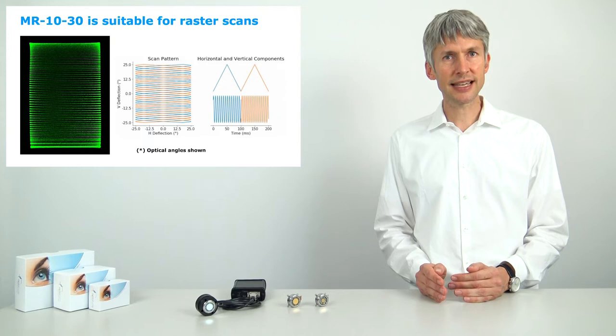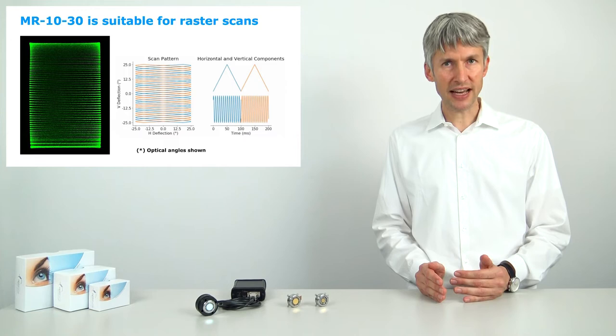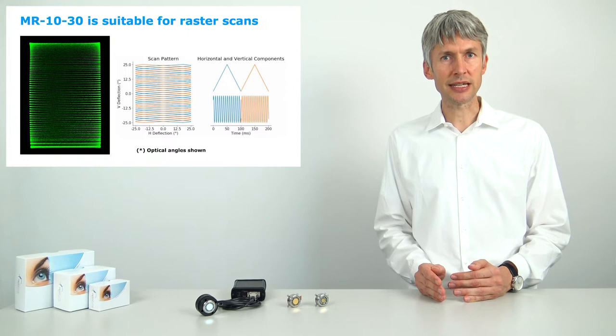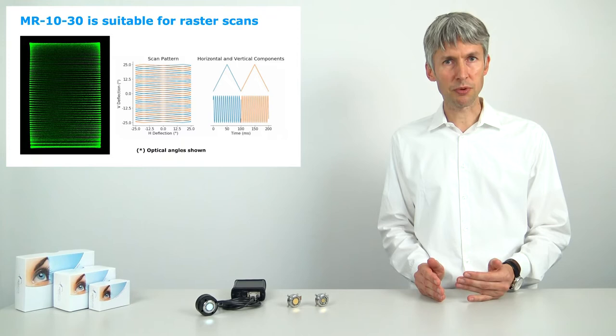In this picture we see the projected scan pattern of a laser hitting the MR-10-30. The resonant fast axis is operated in open loop sine at its fixed resonance frequency of 250 Hz. The non-resonant slow axis is operated in closed loop at 10 Hz triangular.